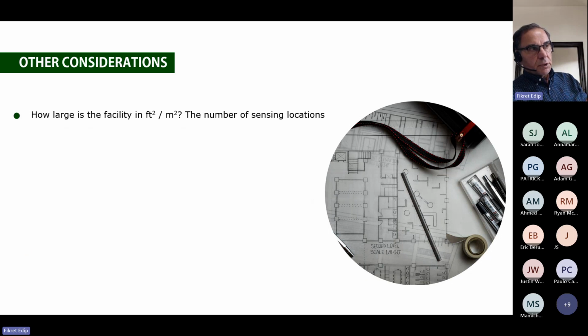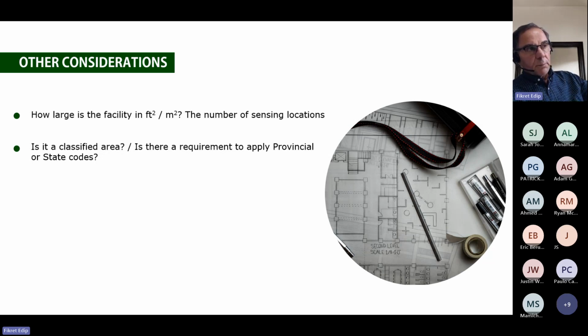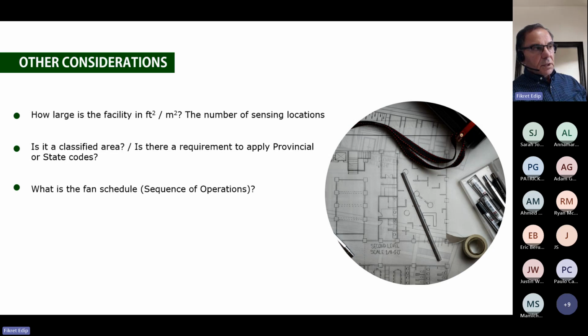There are some considerations you need to pay attention to as a sales engineer. How large is the facility in square footage? And how many sensing locations? Just like fire alarm code: where do I put my sprinklers? How far apart are they? This is exactly the same thing. Is it a classified area, where you need explosion-proof transmitters? Is there a fan schedule, a sequence of operation? You need to ask the engineer, what's my sequence of operation? What do you want me to do when I detect leak gas? Often engineers don't know, so we have to provide that, and later on they can change it.